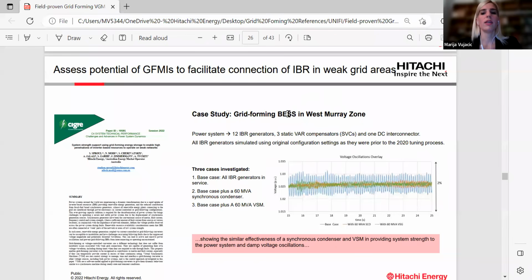So the West Murray zone is part of the NEM, which is characterized as a weak network, and upon a fault, a 0.9 per unit voltage oscillation was noticed. So the EMT model of PowerStore was integrated into the model of the network, and simulation was done considering a 60 MVA synchronous condenser to understand the impact of connecting a synchronous condenser of this size to damp this voltage oscillation. And as you can see here, it was proven that the voltage oscillation was damped quite efficiently.